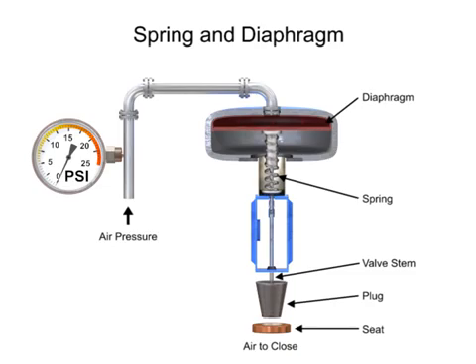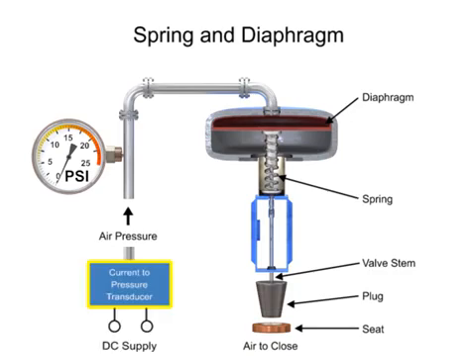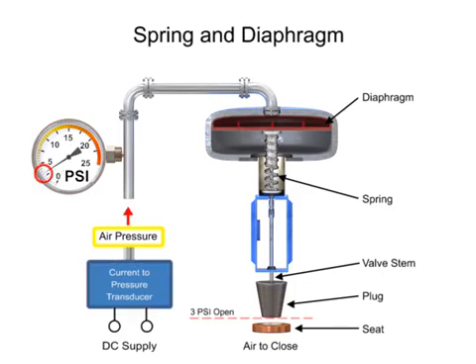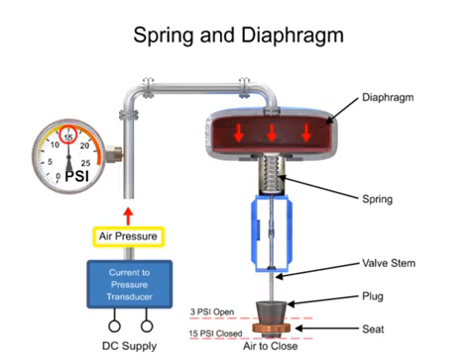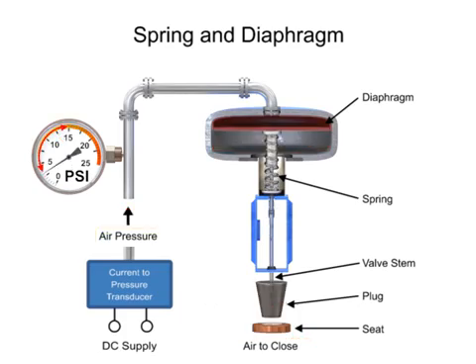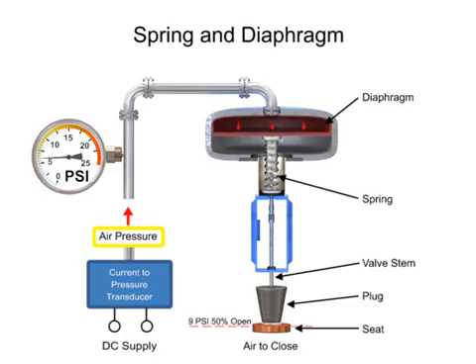To vary the position of the restrictor and flow through the valve, a current to pressure transducer can be used to provide a 3 to 15 PSI signal to the diaphragm. At 3 PSI, the valve is maintained open, and at 15 PSI, the valve is maintained closed. Pressures between the 3 to 15 PSI range proportionally change the flow of the valve. For example, a pressure of 9 PSI applied to the diaphragm moves the spring and valve stem to 50% of operating range.